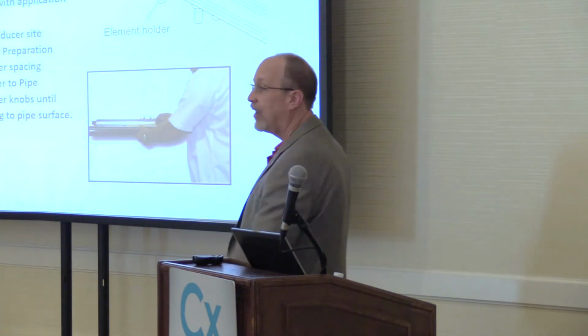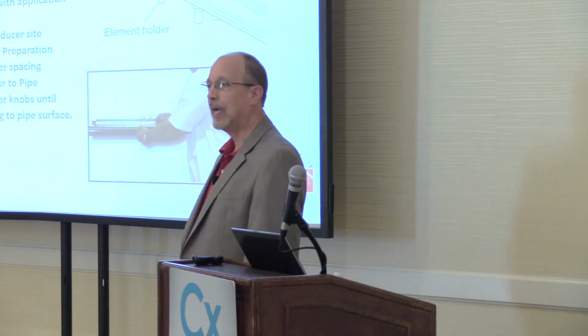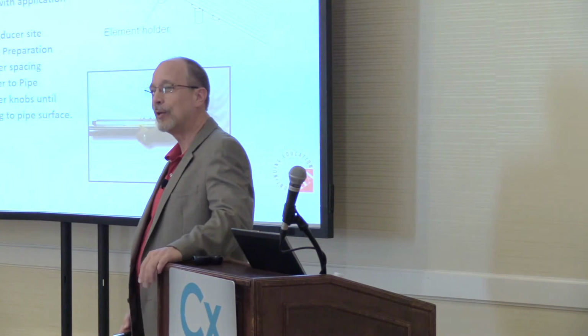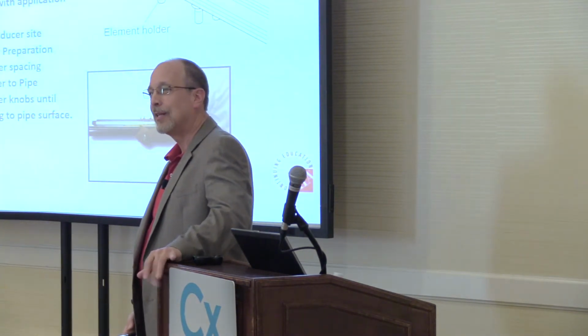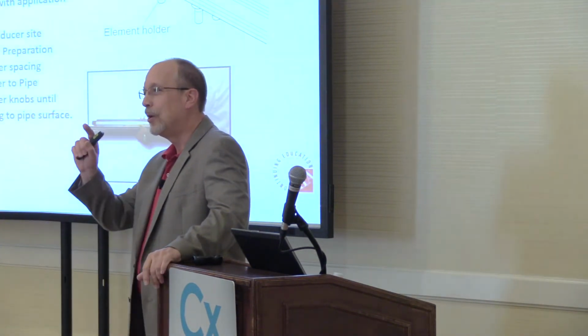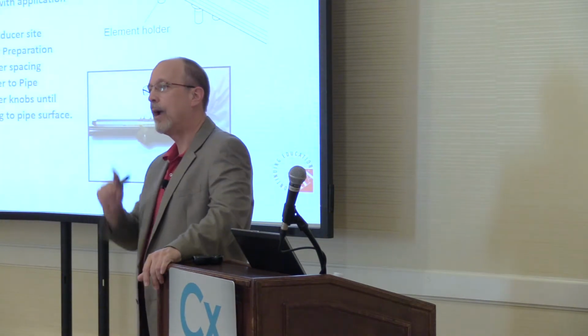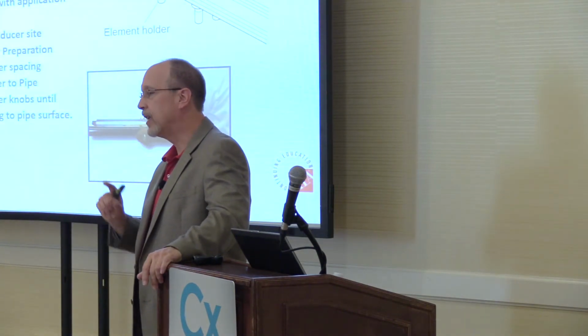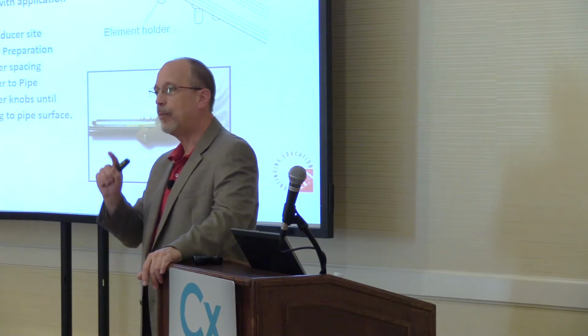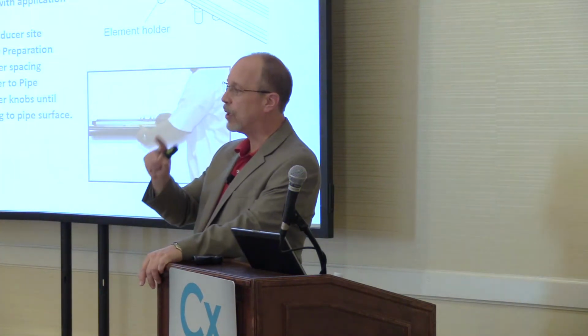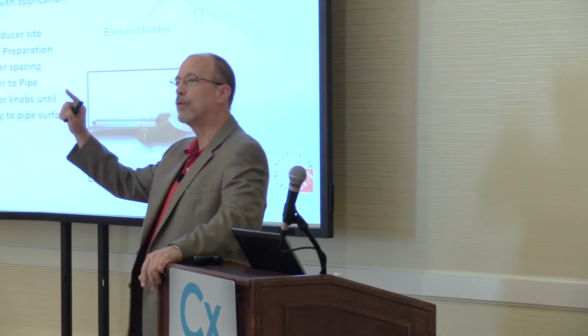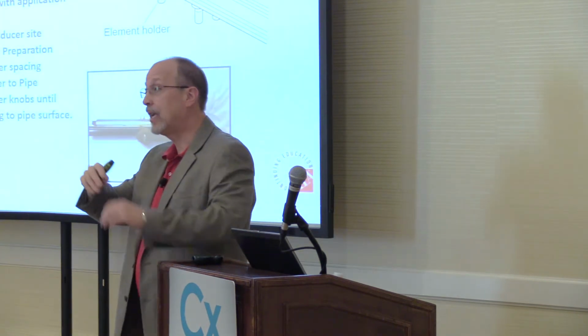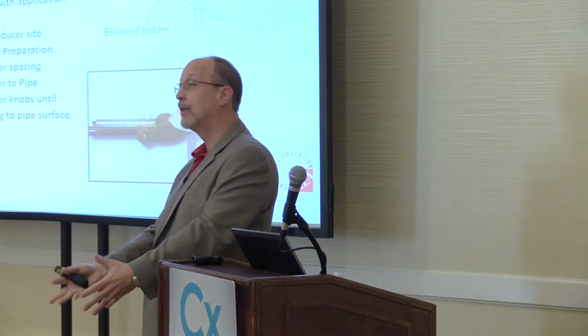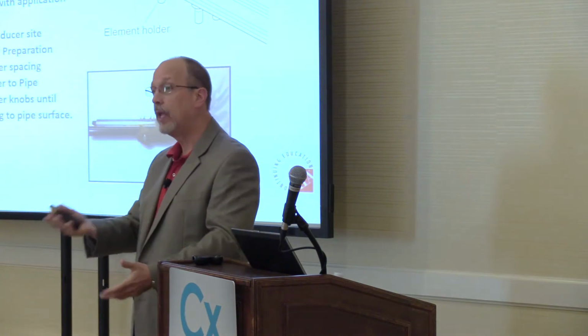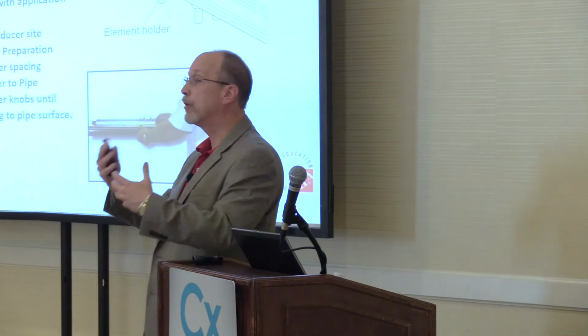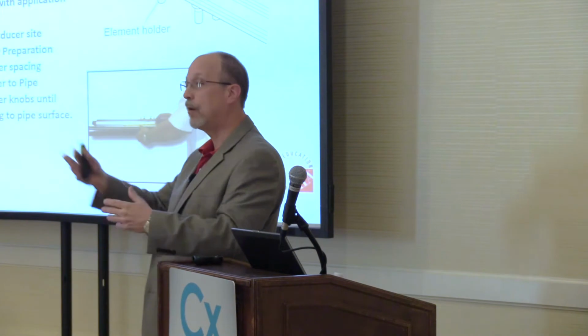And there's all different flavors of grease. I'm the grease king for ultrasonic flow meters. We have 10 different flavors, just like Howard Johnson's there. The best kind of grease to use, the all-around grease, is a silicone grease. And the silicone grease will stay in the pipe under all conditions. If it's really cold, if it's really hot, and if it's really sweaty, and when you take the insulation off the pipe on a warm day like this, you'll get moisture on the surface of the pipe. It'll work through that.